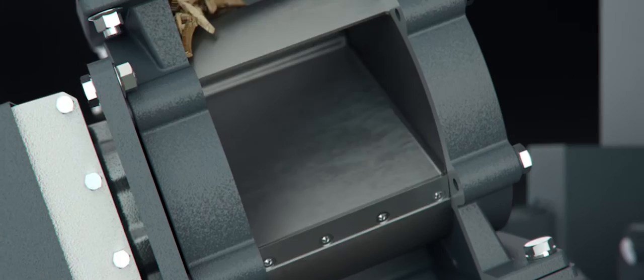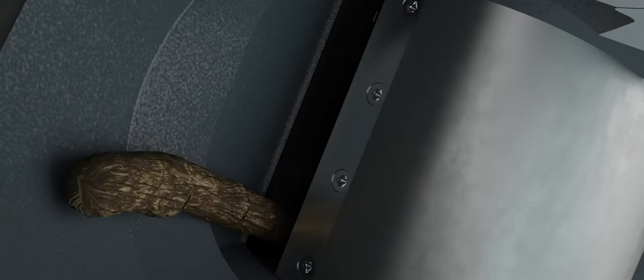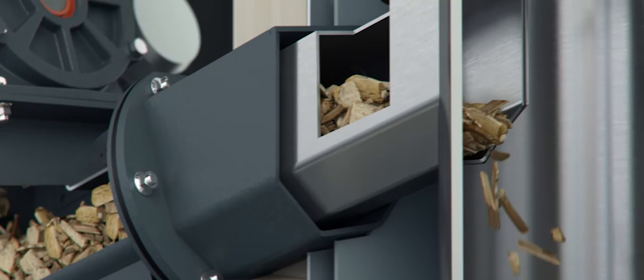The smart way in which the PuroWIN works ensures reliable wood chip transport. Sensors ensure that only pieces of wood which are oversized to be transported into the boiler are cut in the rotary feeder. All motors and drives have infinitely variable control. This protects the blades and components from unnecessary wear and ensures precise fuel metering.